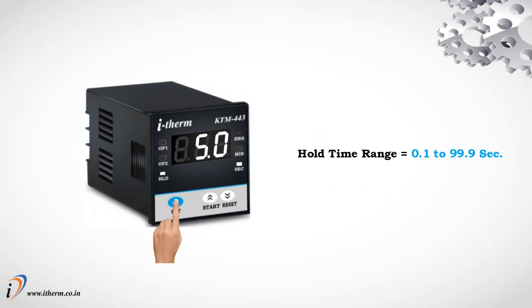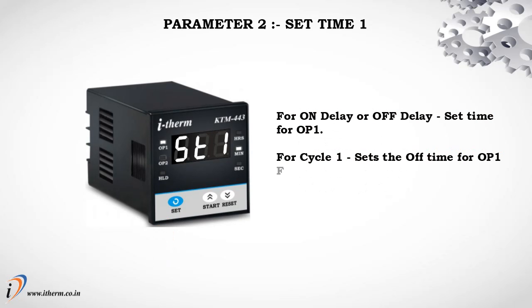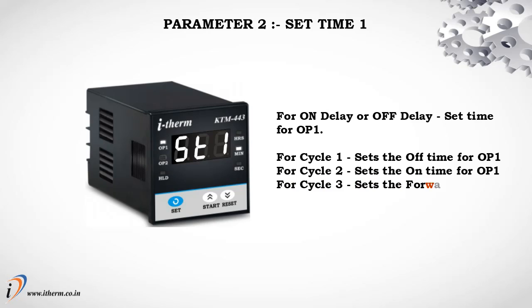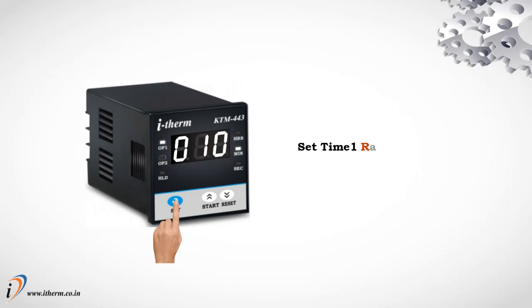Hold time range: 0.1 to 99.9 seconds. Parameter 2: set time 1. For on delay or off delay, sets the time for output 1. For cycle 1, sets the off time for output 1. For cycle 2, sets the on time for output 1. For cycle 3, sets the forward time for output 1. Set time 1 range: 0.01 seconds to 999 hours, depending on range 1.